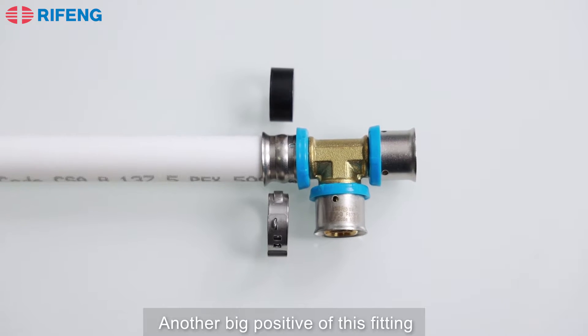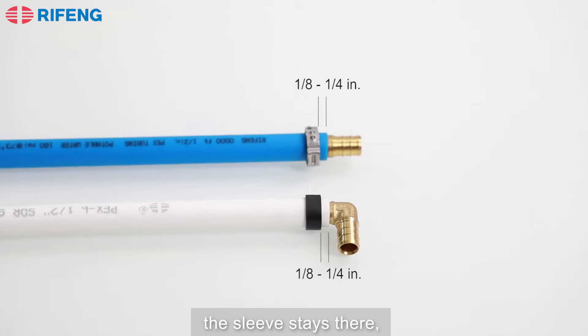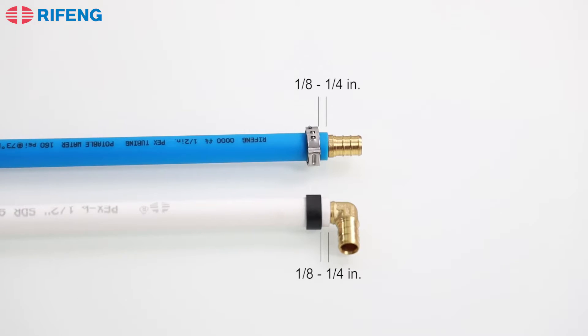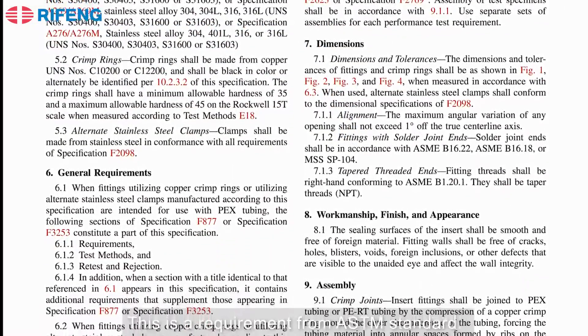Another big positive of this fitting is that when you insert the press fitting on the pipe, the sleeve stays there. But if you use crimp rings or stainless steel clamps, you need to make sure you place them in the right place or there is a leakage risk. This is a requirement from ASTM standard: for fitting sizes 3/8 inch to 1 1/4 inch, the edge of the crimp ring or stainless steel clamp should be 1/8 inch to 1/4 inch from the end of the tubing. So you either judge by experience or measure with a tape — it's risky and inconvenient.